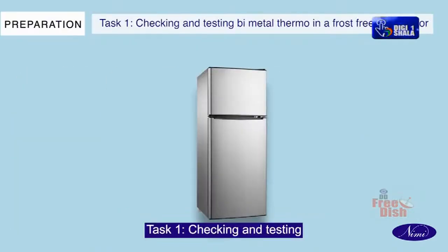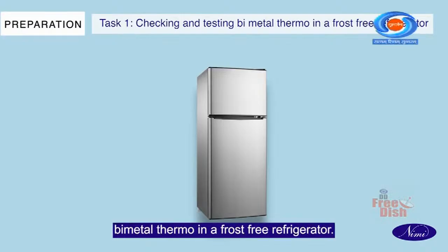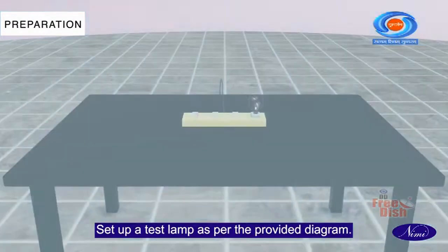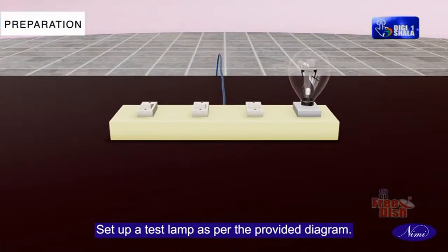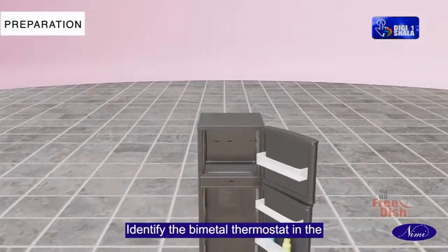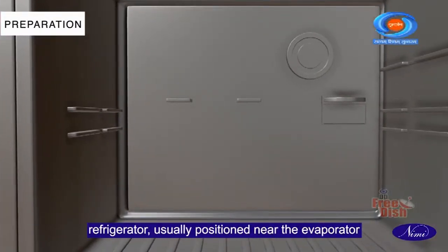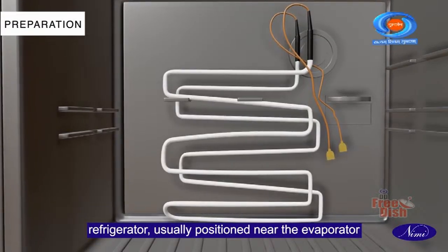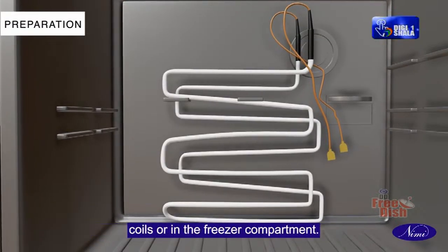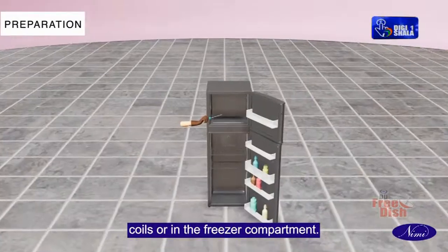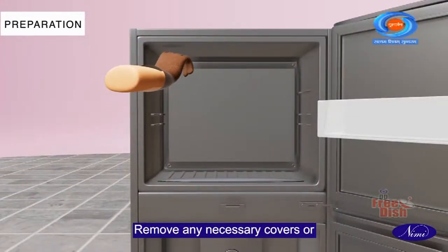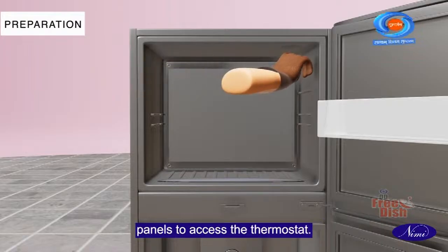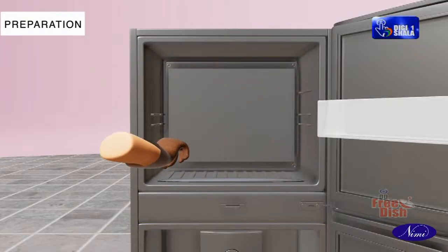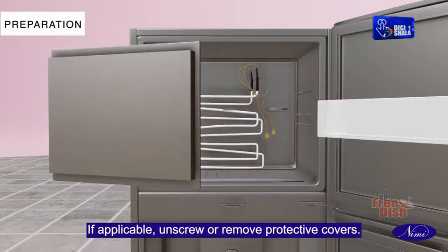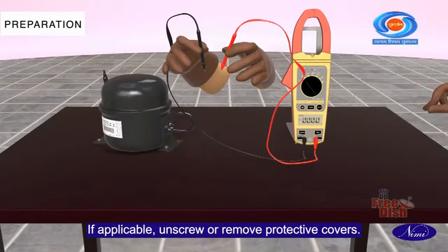Task 1. Checking and testing bimetal thermo in a frost-free refrigerator. Set up a test lamp as per the provided diagram. Identify the bimetal thermostat in the refrigerator, usually positioned near the evaporator coils or in the freezer compartment. Remove any necessary covers or panels to access the thermostat. If applicable, unscrew or remove protective covers.